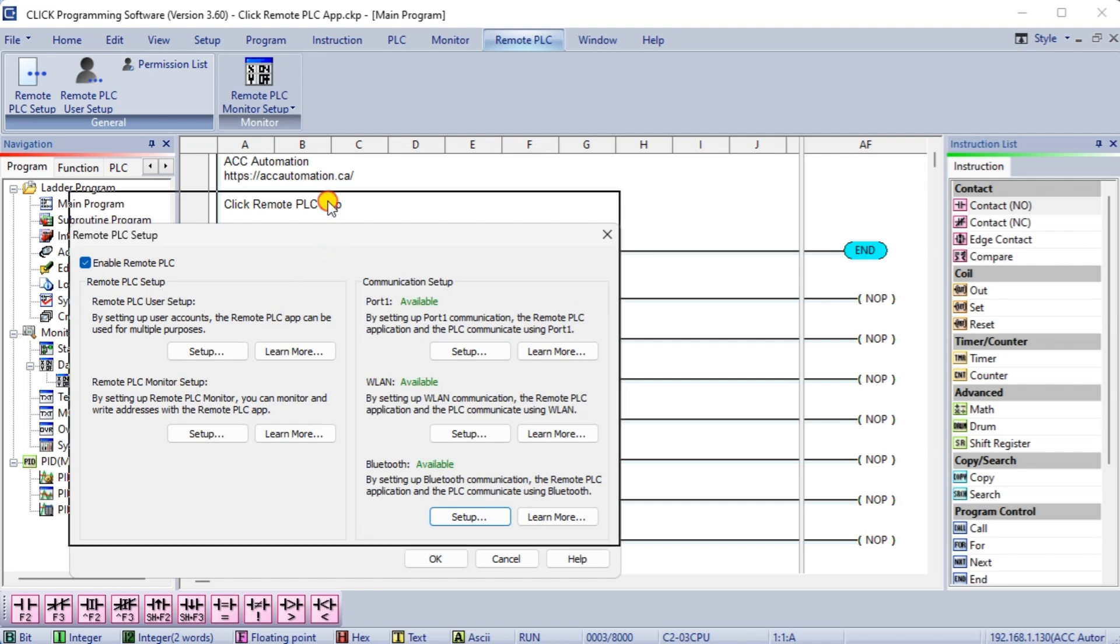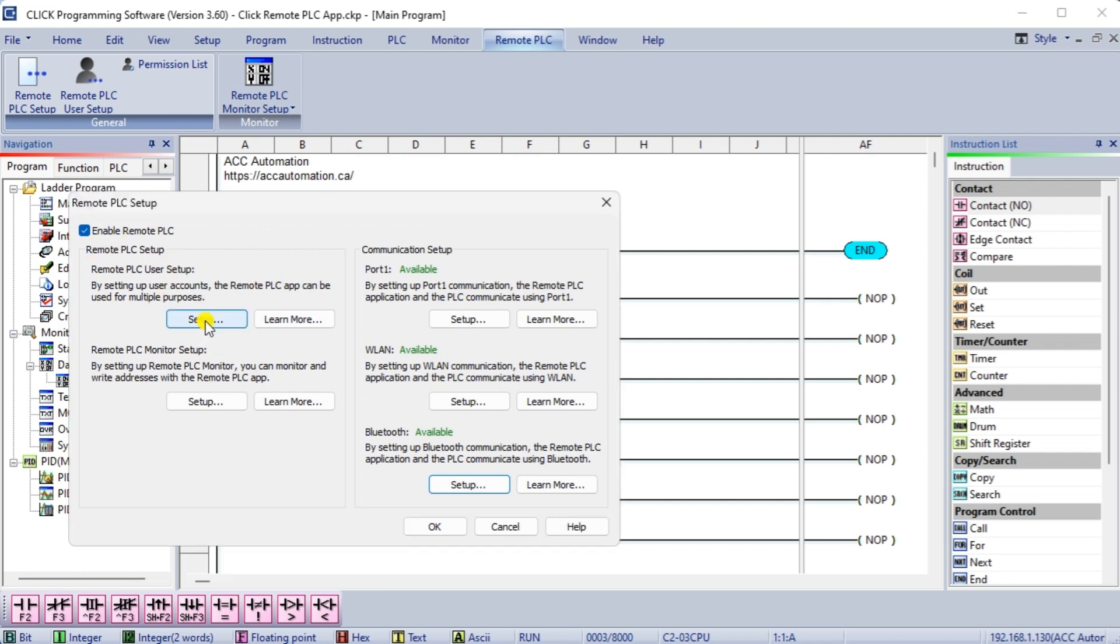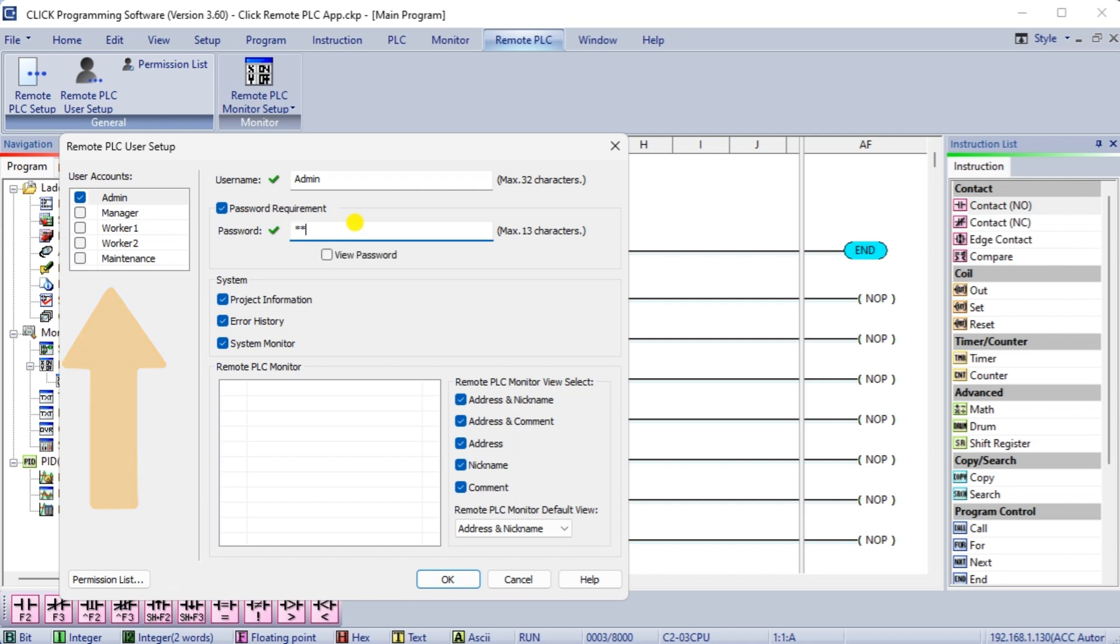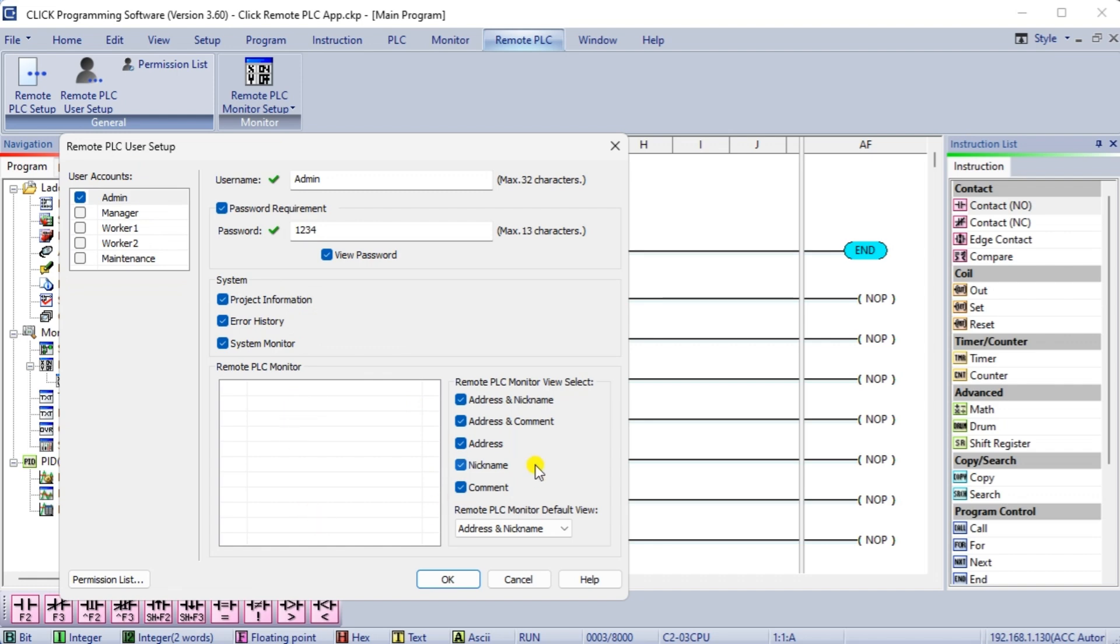Select setup under the remote user. Remote user setup window will be displayed. This screen will allow us to put in five different profiles of users for the remote application and select access to certain information. System project information, error history, and system monitor can be selected for each profile. A password must be assigned to each profile to set it up. Our demonstration will turn on everything for the admin profile and we will use password of 1234. Select ok.